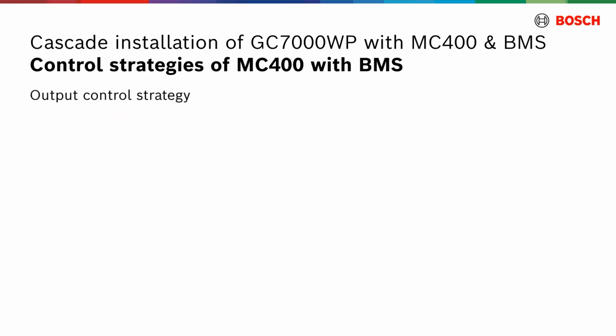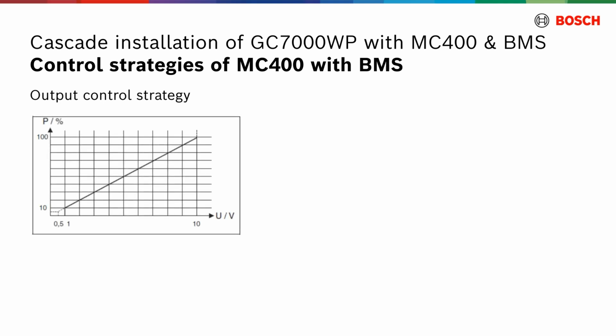Output control strategy. For the output control strategy, there is a linear relationship between the 0 to 10 volt signal and the required power as a percentage of the maximum system output. There is no internal temperature control in the MC400. The cascade output is defined via the 0 to 10 volt interface, and thus also the modulation behavior. Sensor T0 is only used to monitor the maximum flow temperature at the low loss header.